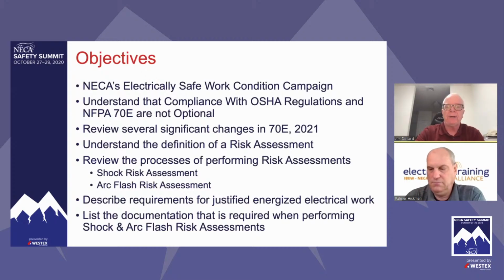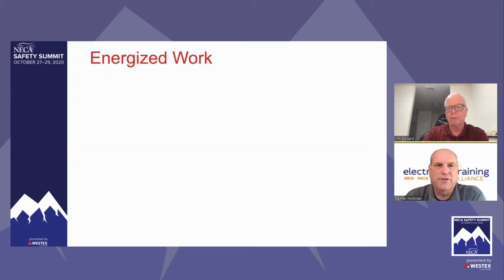But when we do tasks such as troubleshooting, using a test instrument, a voltage tester, we have to do a shock risk assessment. We have to do an arc flash risk assessment, and we have to document those. We're not documenting them today. We have to do that. We have to get that done because NFPA 70E also requires you to audit all of your field work. And that's the only way that you're going to be able to do that.